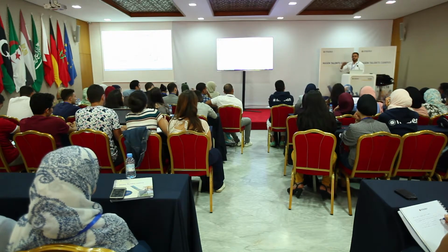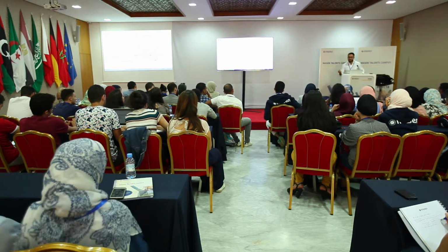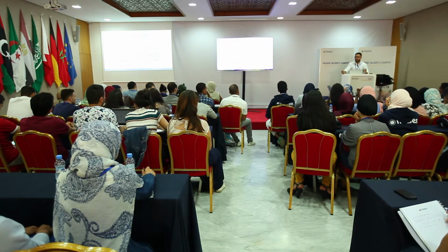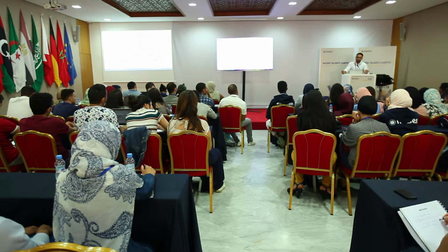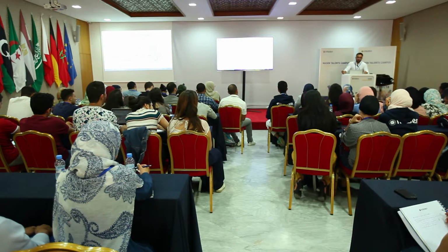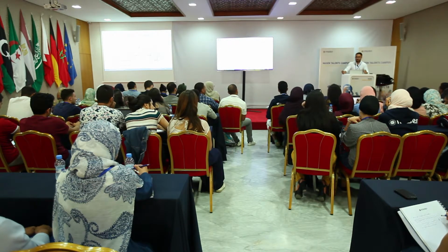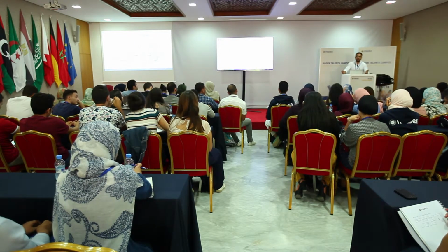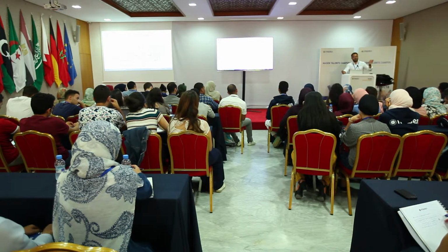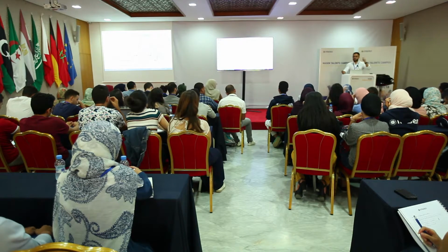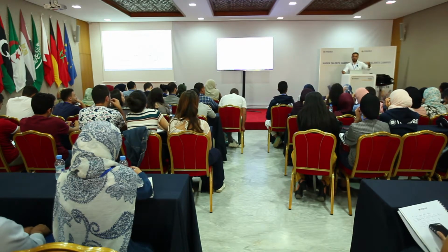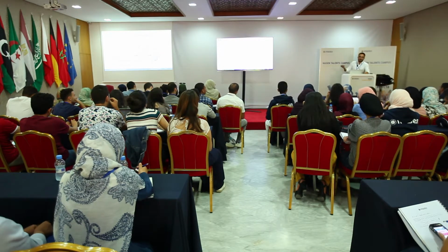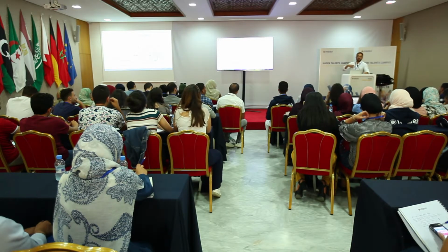Now, a PV plant cannot last 40 years. The reason is that the degradation of modules is such that in year 25, usually for all the technologies that we have commercially available, the plant produces 80% of the installed capacity. There's a degradation in materials. This is not because of the way we clean it or operate it. The material degrades. And that's another thing that has really been a problem for CSP: CSP plants are given contract lengths of the same length as PV. But in reality, a CSP plant, of course, would be able to offer a cheaper price if we were able to secure a contract for 40 years instead.